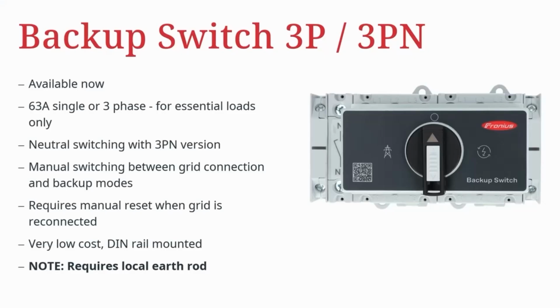The next option available is our Fronius backup switch, and this is positioned for essential loads. So this is mounted external to the inverter and enables certain loads which are essential on the site to remain connected when there is a grid failure. When the grid fails, simply switch between the grid connection mode and the backup mode manually.